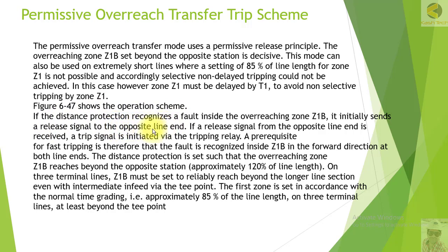If the distance protection recognizes a fault inside overreaching zone Z1B, it initiates a release signal to the opposite line end. If a release signal from the opposite line end is received, a trip signal is initiated via the tripping relay. A prerequisite for fast tripping is therefore that the fault is recognized inside Z1B in the forward direction at both line ends. The distance protection is set such that overreaching zone Z1B reaches beyond the opposite station, approximately 120% of the line length.